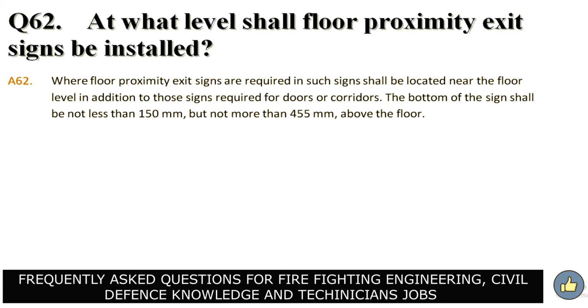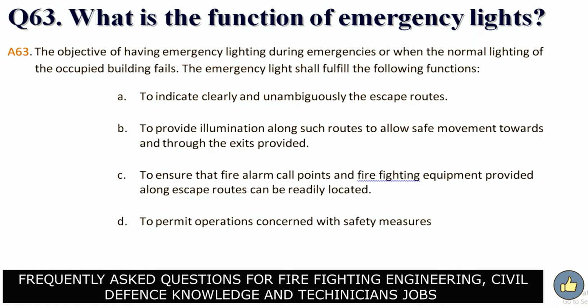At what level shall floor proximity exit signs be installed? Answer. Where floor proximity exit signs are required, such signs shall be located near the floor level in addition to those signs required for doors or corridors. The bottom of the sign shall be not less than 150 millimeters but not more than 455 millimeters above the floor. What is the function of emergency lights?